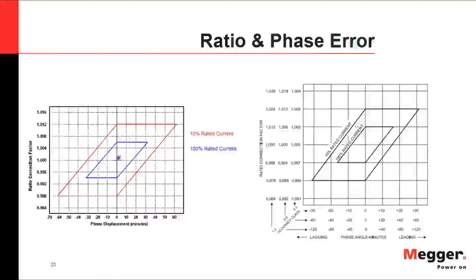One advantage from IEEE is the provision of parallelograms, allowing you to plot both the magnitude value and the phase deviation angle on a graph. You can visually confirm that at 100% rated current and at 10% rated current your transformer complies with the standard, analyzing results against the specification for both phase deviation values and magnitude.